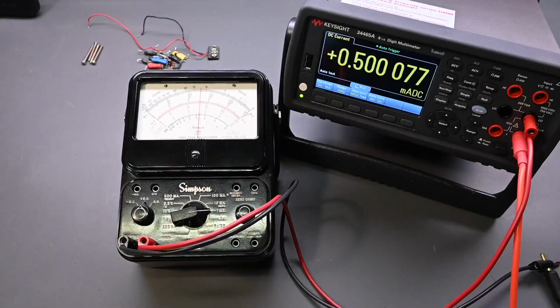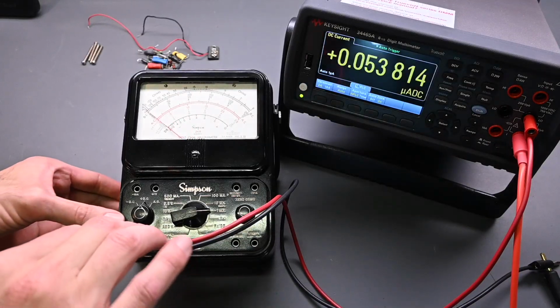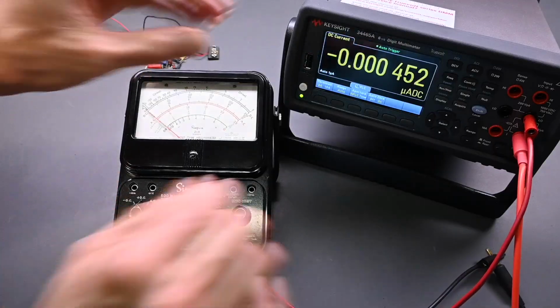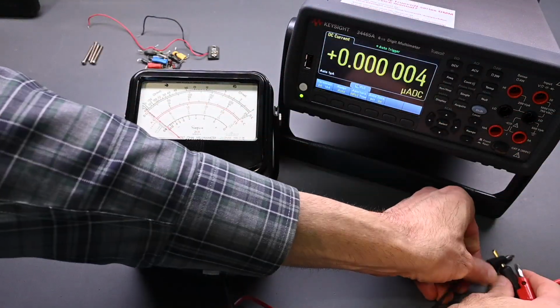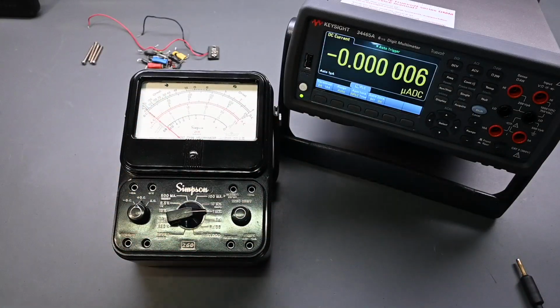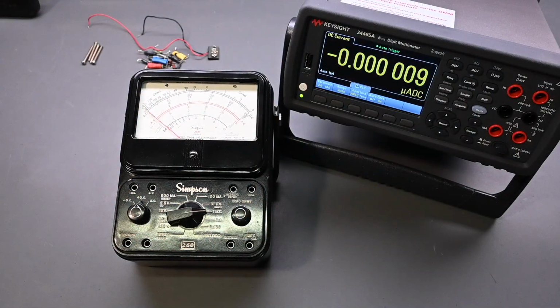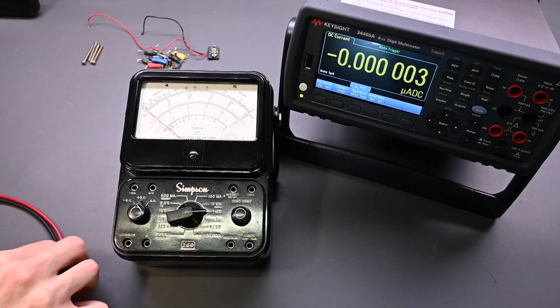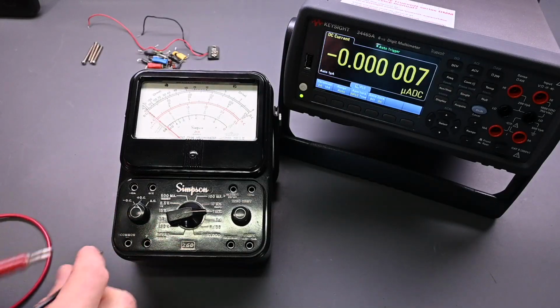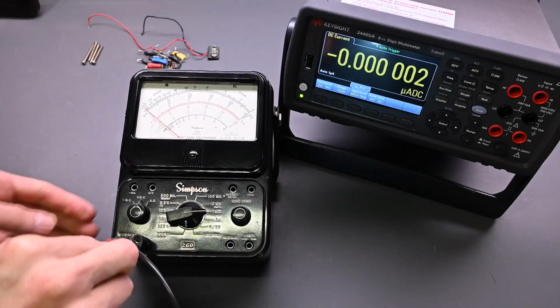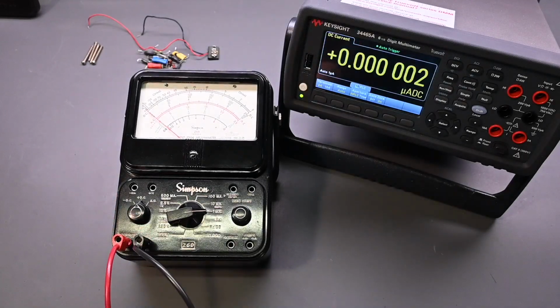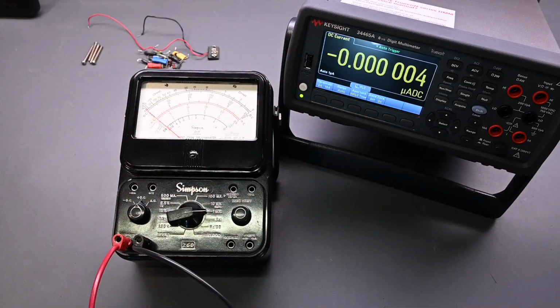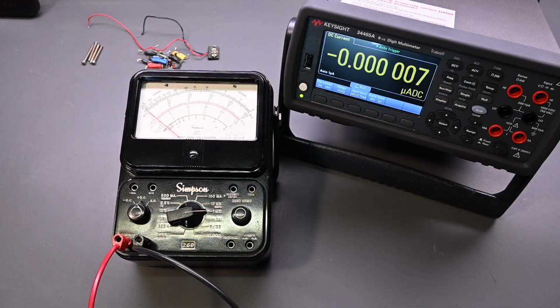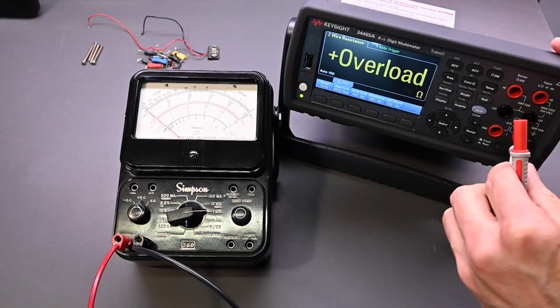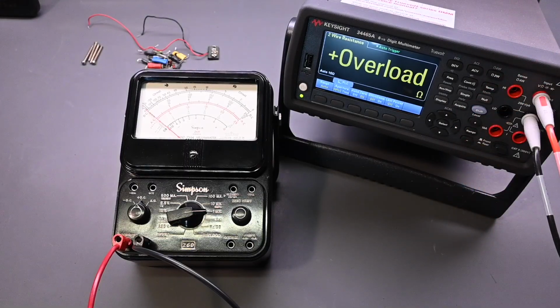So I'm going to turn the Keysight back off, standby mode. And what I need to do is change this around just a little bit here. Pardon all of the test lead rearranging. Just kind of change this around here. So of course, for a resistance reading, both meters cannot be connected to the same resistor, so one at a time. So I just have a couple sample resistors, and we'll compare the reading on the Keysight and what we get over here. And on this over here, what I need to do, back to mode there, like so.